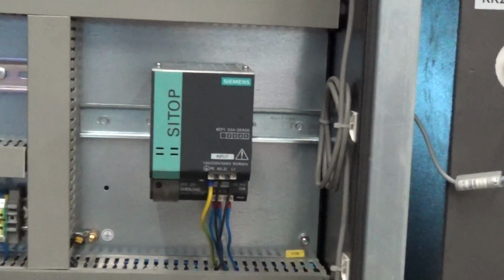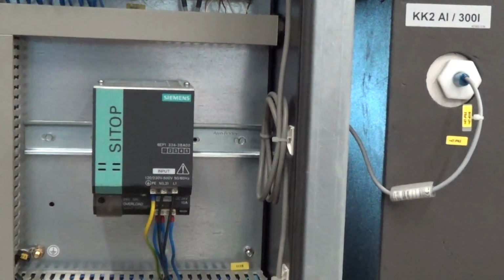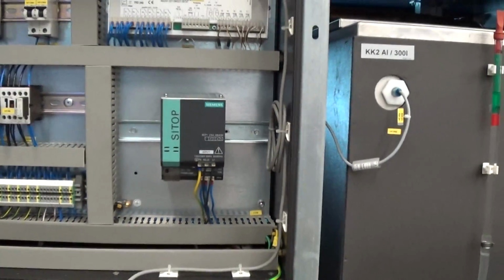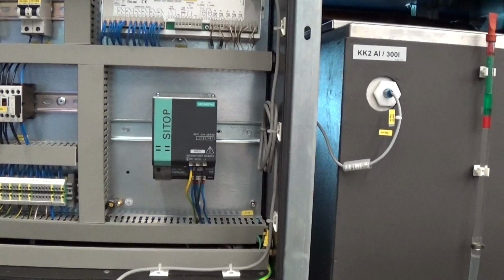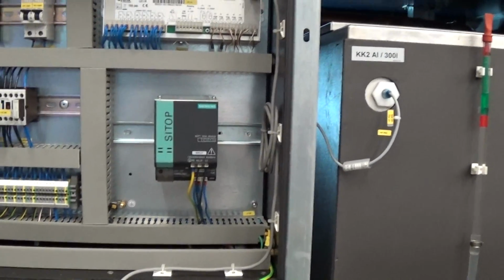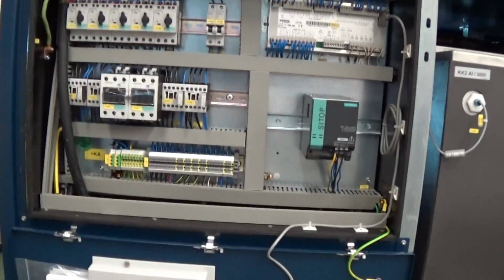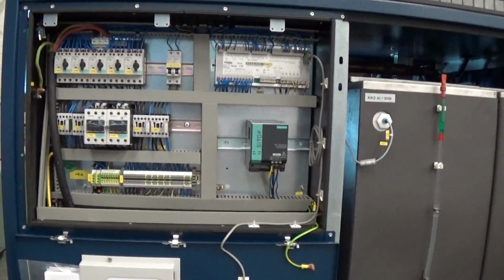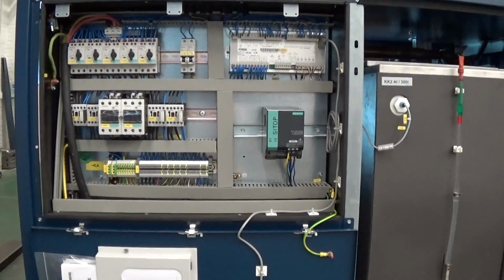This here is the controller power supply that we installed. That was the only thing really special about this unit, in that it was assuming it was getting its controller power from a process machine that it was kind of designed around. Other than that, it's a pretty generic refrigeration and chiller setup, with the exception that it's kind of, you know, two 12 horsepower chillers side by side. So I'm going to come back, video number 2 in a second. I'm going to power this up.